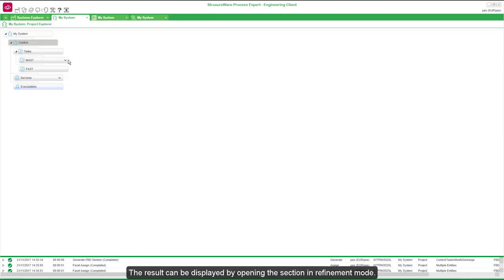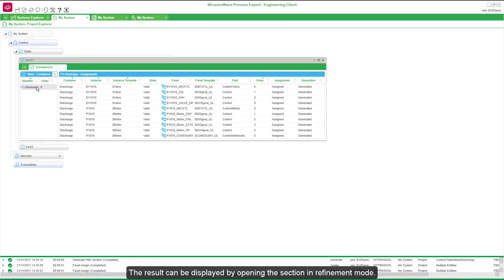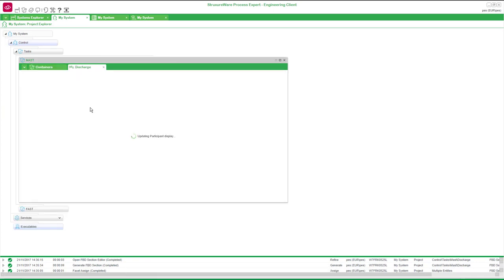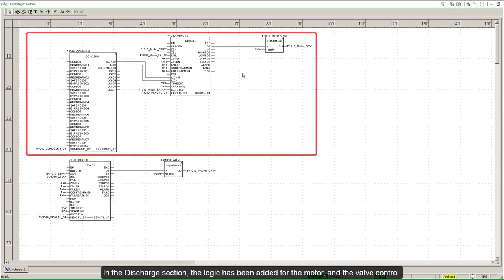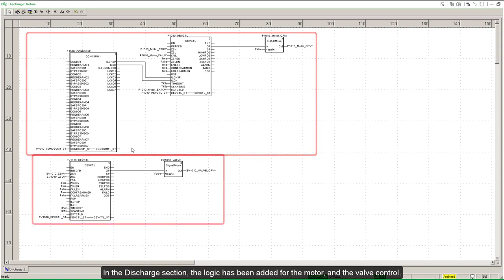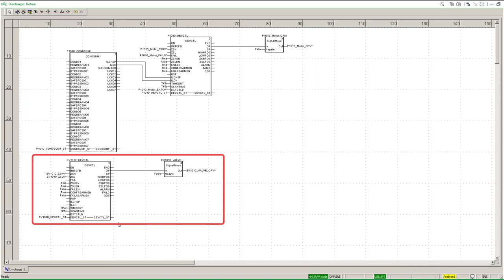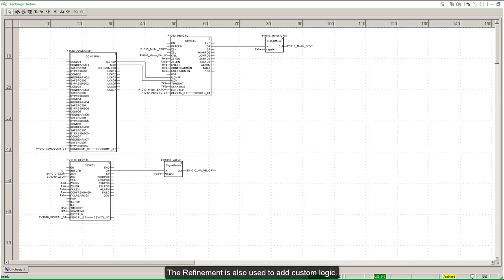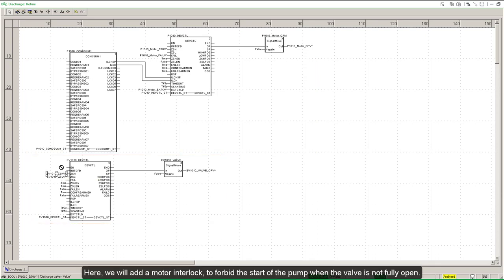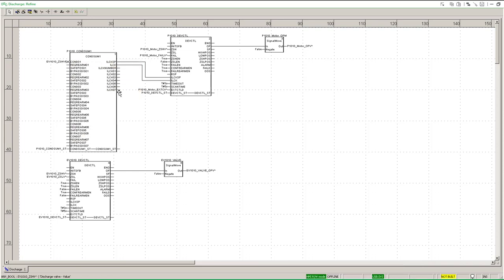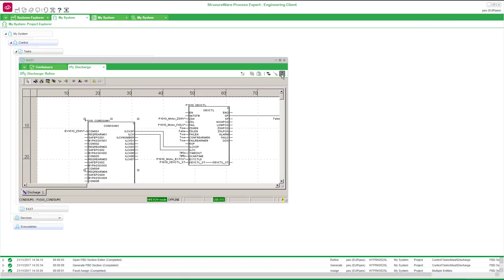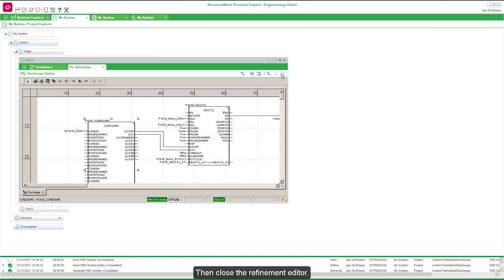The result can be displayed by opening the section in refinement mode. In the Discharge section, the logic has been added for the motor and the valve control. The refinement is also used to add custom logic. Here we will add a motor interlock to forbid the start of the pump when the valve is not fully open. Modifications must be saved, then close the refinement editor.